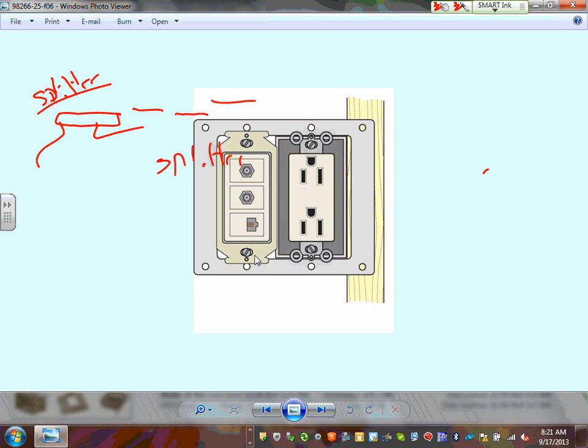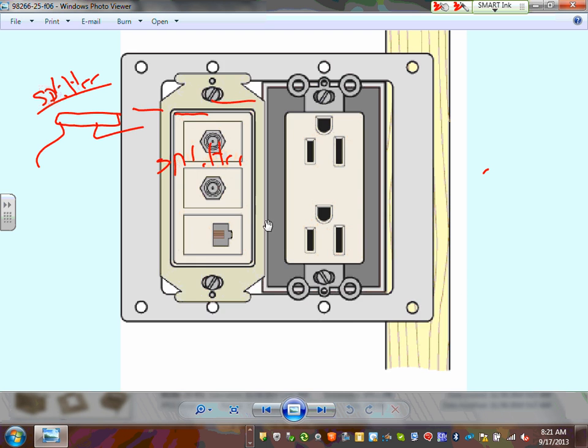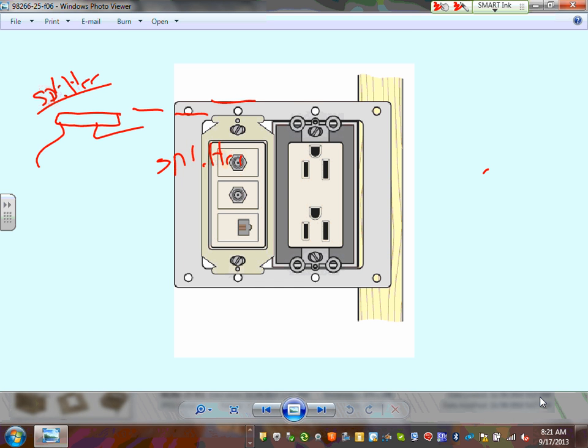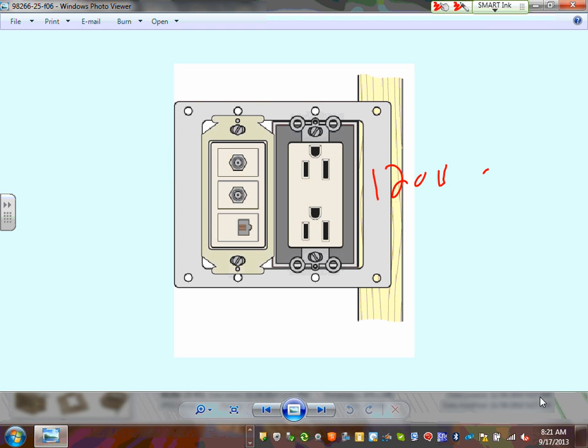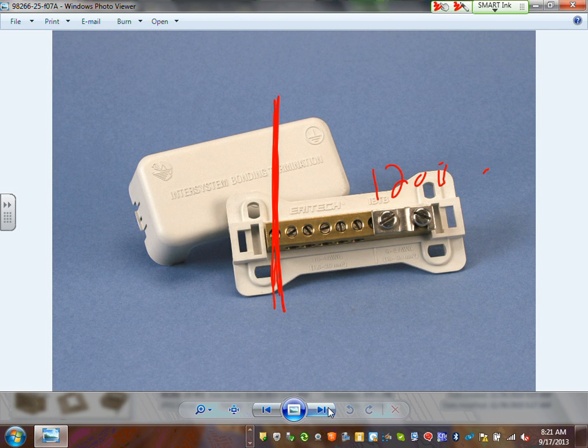Antennas, dishes. If you put an outlet and a phone in the same box, can you guys see that? Can I have one box which houses my 120 receptacle as well as my low voltage, as long as the box has separation? Can you guys see that separation? You can have the same box as long as there is separation between them, or you can have a cover that covers them, one in a box, one not in a box, but as long as they're separated, that's what you need.